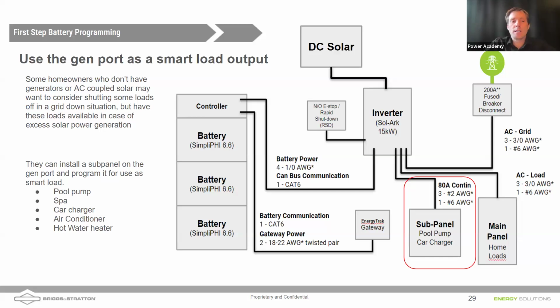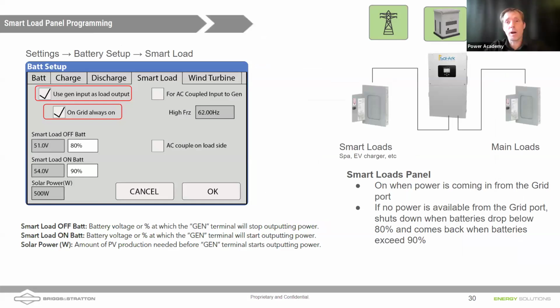You might not want to keep the spa on. You might not want to be charging your car, which might have a 100 kilowatt hour battery in it, off your 20 kilowatt hour home backup, right? So you can have those car chargers, the air conditioner, the spa, the pool pump shut off automatically if you wire those into a sub panel. And so this is one of my favorite uses of that generator port on the inverter, is using it as a smart load panel.